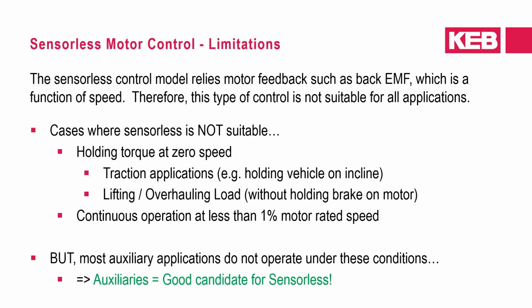I should make note, though, that sensorless control has its limitations and is not suitable for all applications. Since the motor model relies on voltage feedback, which is a function of speed, applications involving holding torque at zero speed or continuous operation at less than 1% of motor rated speed are not suggested. In these cases, encoder feedback should be used and is not currently supported by the T6. But most auxiliaries do not operate under these conditions, and sensorless control is a good candidate for these applications.